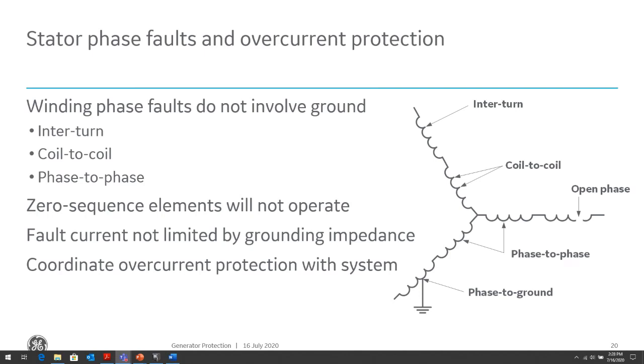So phase faults are not limited by the type of grounding we discuss, right? Because phase faults don't involve ground, the grounding resistor, whether it's low impedance or high impedance, does not come into the picture. The GSU does not provide isolation for phase faults, so we will see phase faults within our power system reflected into the generator. Overcurrent protection requires coordination for system faults and will be slow. Damage can be catastrophic if the fault currents are high and are not removed immediately. So whatever protection we have for phase faults within the generator zone, we need to be able to isolate quickly.